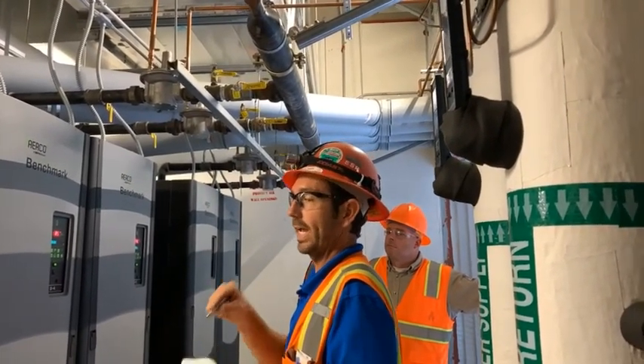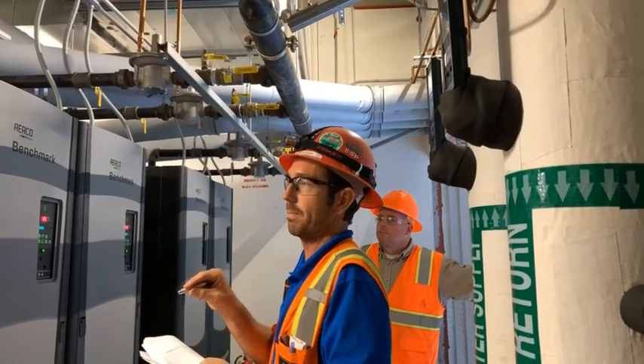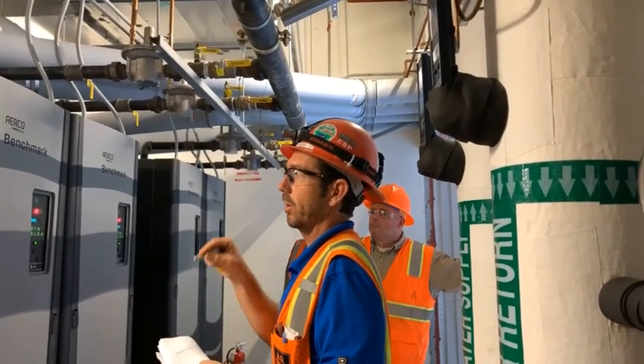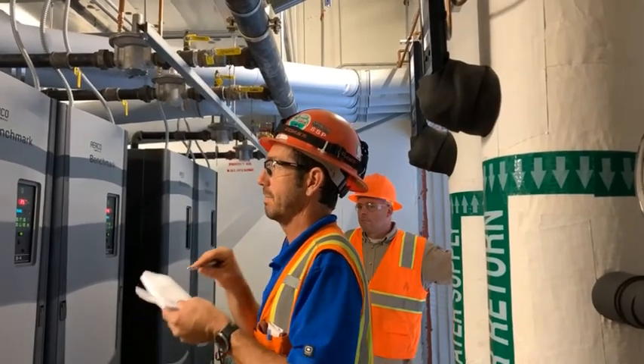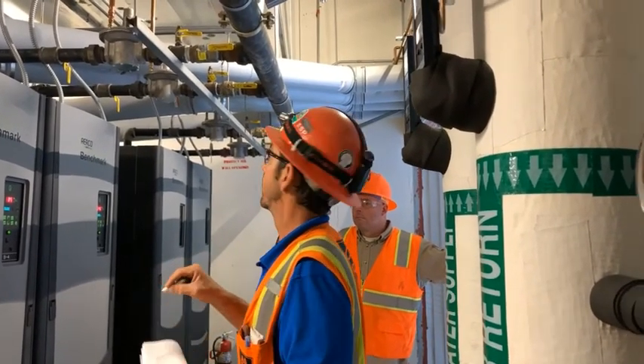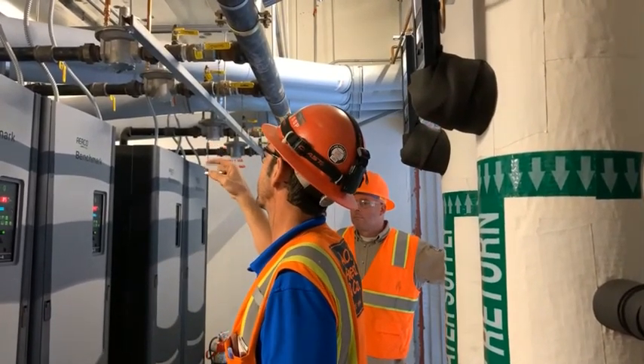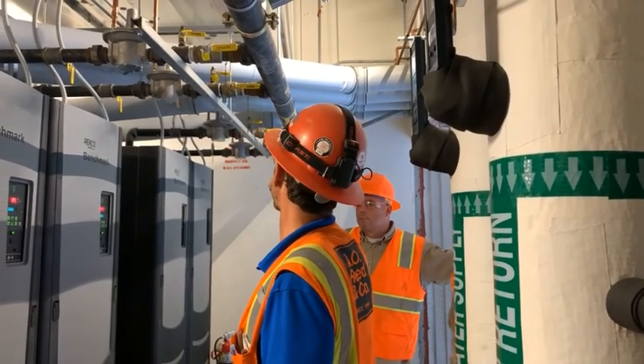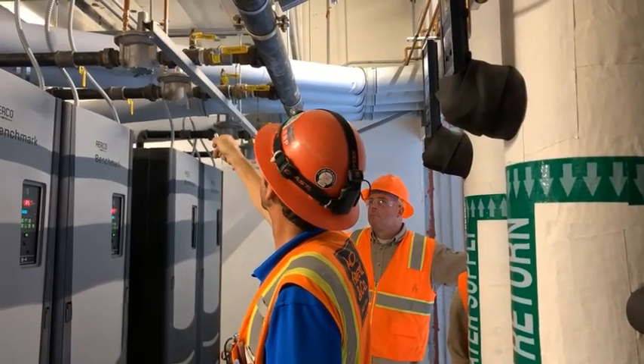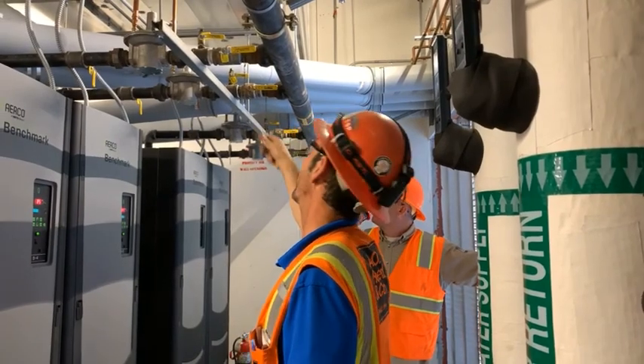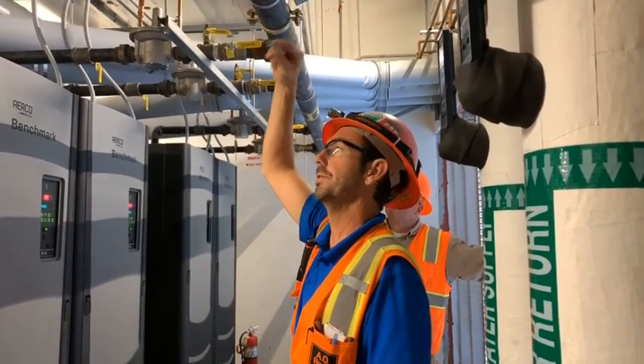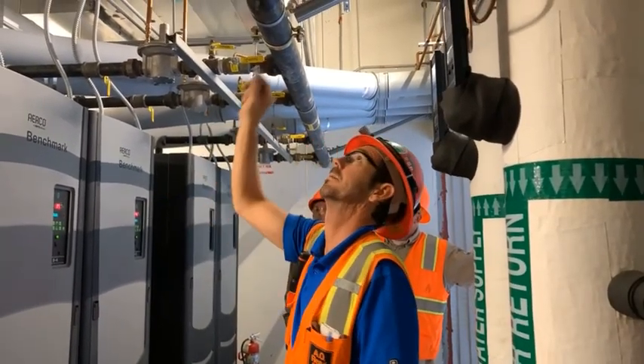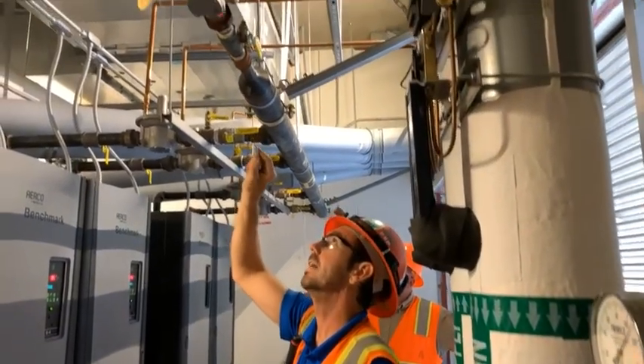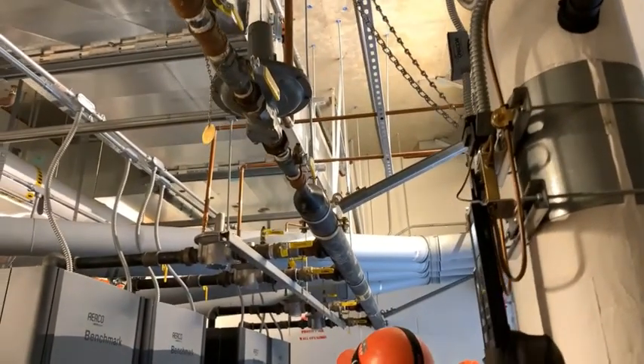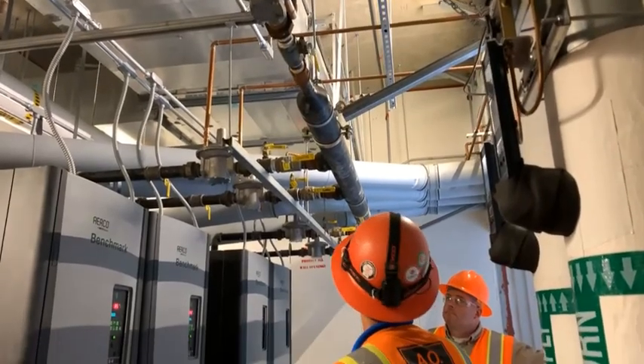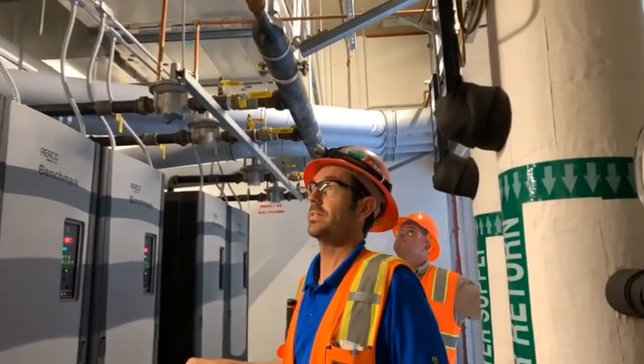They maintain a gas pressure through them. Does that make sense? They don't close off, they don't reduce pressure. They just maintain flow, okay? Maintain the gas flow to each boiler, okay? We have test boards in front of them. So the only regulator you're setting for reducing pressure, for the maximum pressure on the boiler, is going to be this guy right here. And he's sized for the boiler, okay? That's all the information for this 1 mechanical room.